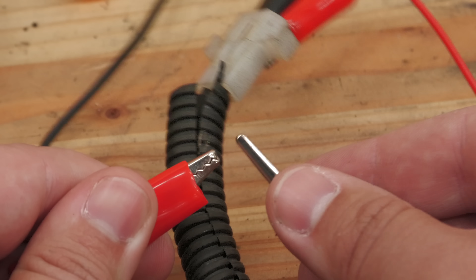You can't just close contactors and connect everything up immediately. For one thing, the contacts will spark, a lot more than what you're seeing here at 48 volts. Every time it sparks, it degrades and wears out the contacts. Also, if you just close contactors, a lot of current will rush into these high voltage loads, and that inrush current can damage sensitive electronics.